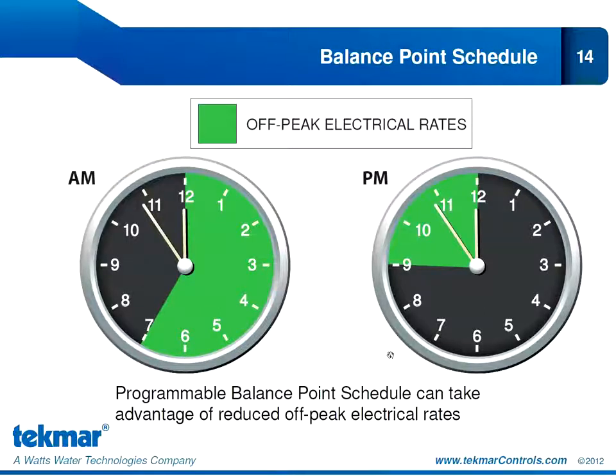Balance point schedule is a new feature for Tekmar. As far as I know, the 557 is the only thermostat on the market that incorporates this function. Let's say it's cold outside, but we're still above our balance point threshold. So the heat pump is still operating with some efficiency advantage. And our utility company is offering reduced off-peak electrical rates. So in our diagram, we're showing those reduced rates from 9 p.m. to 7 a.m. It may make financial sense for us to only run our heat pump during those off-peak times when we're getting a financial incentive to do so.